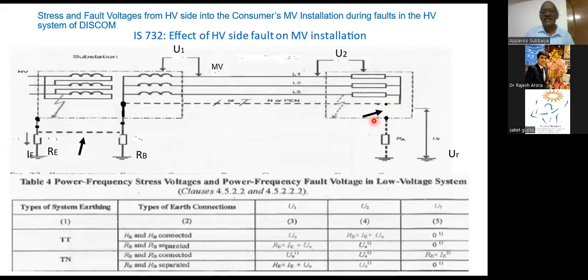So what will happen? See, here in TT, what will be the impressed voltages? Please don't pay much concentration on the formula and other things. What I can say is, if you have a TT system, the U2 is the voltage impressed. Any fault here will impress a voltage on the supplier transformer and the consumer's equipment, and these are known as the voltage impressed. These are the stress voltages that can make your equipment fail. And another thing is the fault voltage. This is a touch voltage. Due to interconnection, there could be a chance of touch voltage, because this will be referenced to this. So this touch voltage Uf will be more.